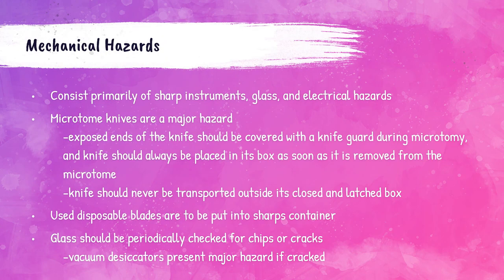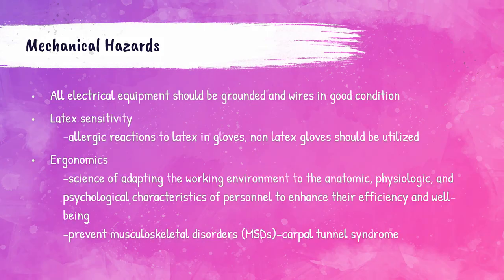Mechanical hazards in the laboratory consist of sharp instruments, glass, and electrical hazards. Microtome knives are a major hazard in the histology laboratory — exposed ends should be kept covered with a guard during microtomy, and as soon as removed from the microtome, the knife should be placed in its box. The knife should never be transported outside its closed and latched box. Used disposable blades should be discarded in a puncture-resistant sharps container. All glass should be periodically checked for chips or cracks.